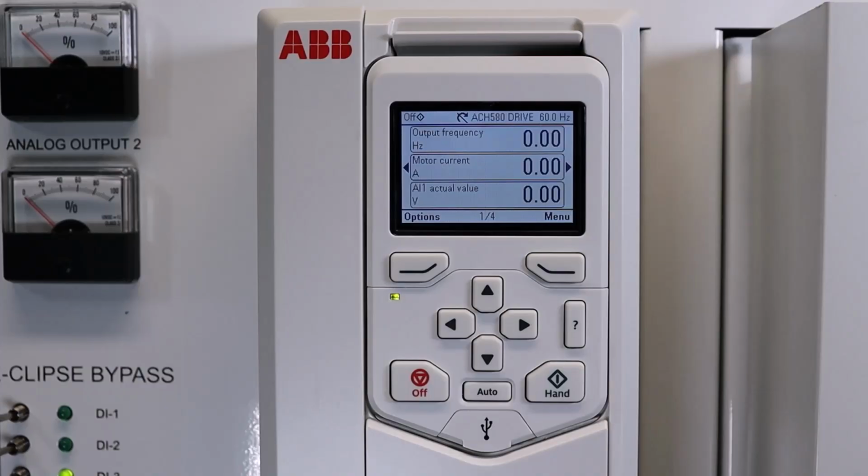What we can do now is we can tell the customer that there is a wiring problem. It's not coming to the drive, the information. And let's say the customer figures it out and then fixes it. That was a wire down at the Freezestat or something like that wasn't connected.